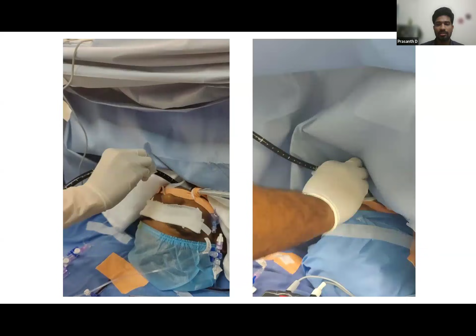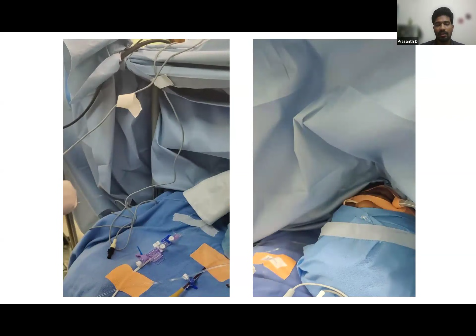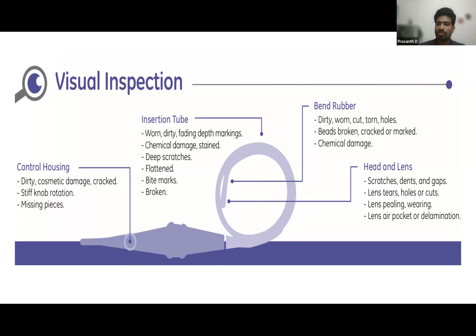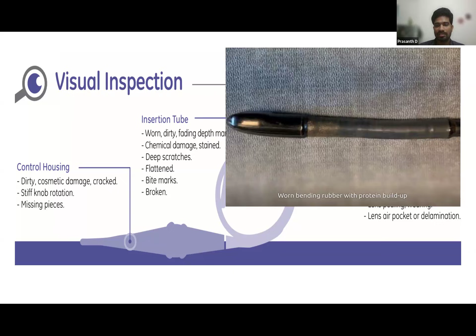After removal, we have to check the probe. We have to clean the probe, wipe off the patient's secretions and lignocaine jelly, and assess from the tip to the shaft for any bite marks or any other injury. Visual inspection is necessary for all parts of the TEE probe: the control housing, for any dirt, cracks or missing pieces; and the shaft, for any bite marks, breakage or chemical damage. The bending portion should be checked, and finally the lens tip should be checked. Sometimes the bending rubber will have protein build-up because of inadequate disinfectant usage.